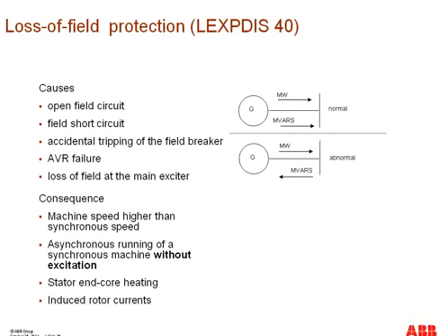So let's talk about the loss of field protection. The IEC 61850 logical node for loss of field protection would be LEXPDIS, and the ANSI number is 40 for this loss of field protection.